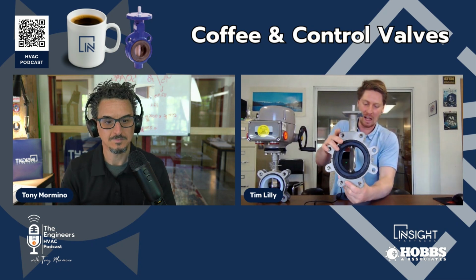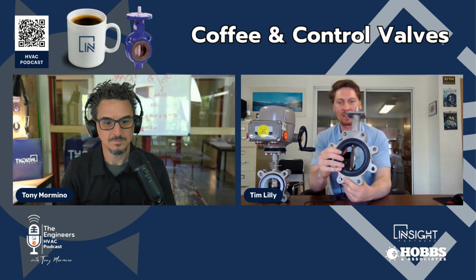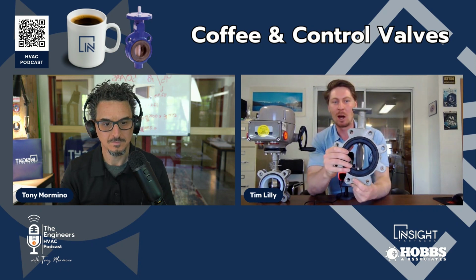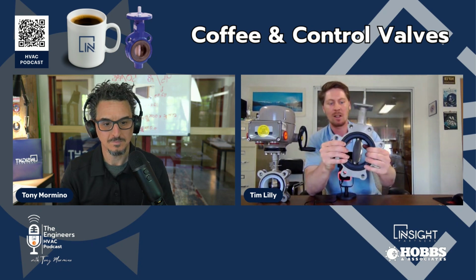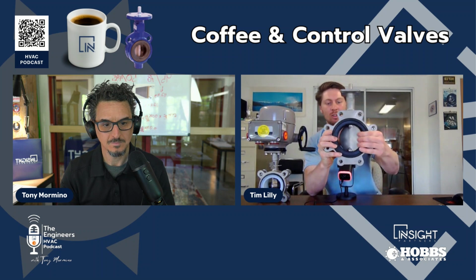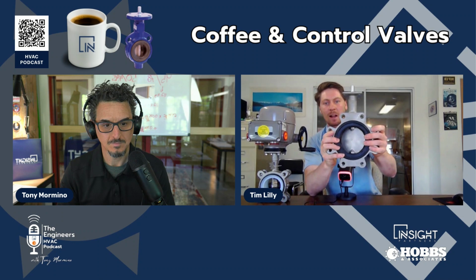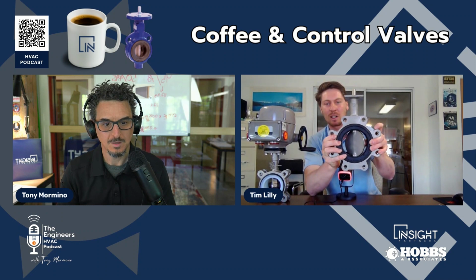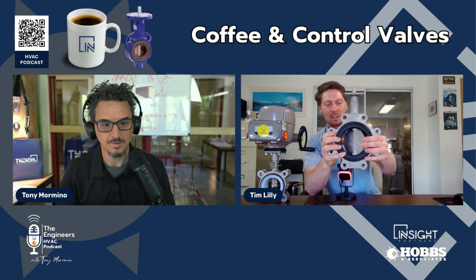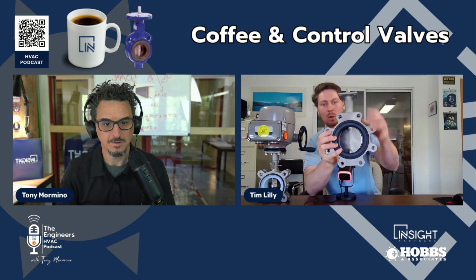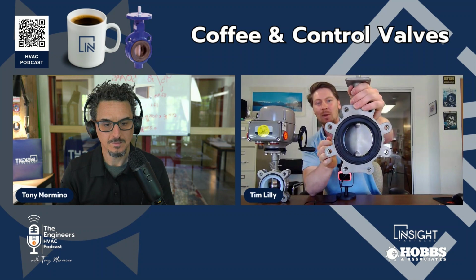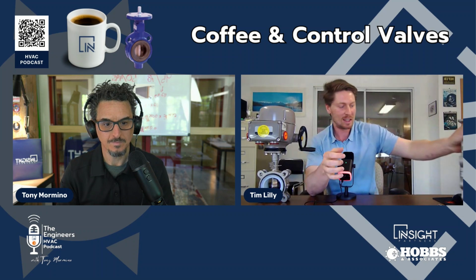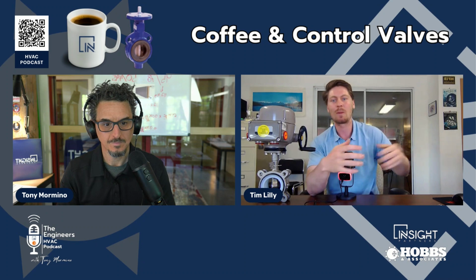I know some of the people listening to this podcast probably install a lot of butterfly valves. The number one reason a butterfly valve fails, Tony, is that when you go to install it, you install it in the closed position, and then you put it between your two flanges, you clamp down on it, and the first time you come out of the seat, you rip your liner and you start leaking before you even run water through it. So if you're listening and you can install your butterfly valve at about 3% open, just enough to be outside of that liner, you're going to extend the life of your butterfly valve tremendously.